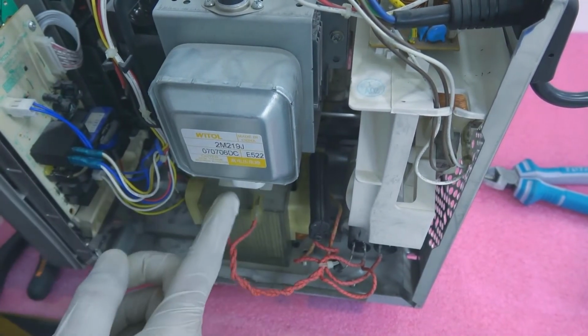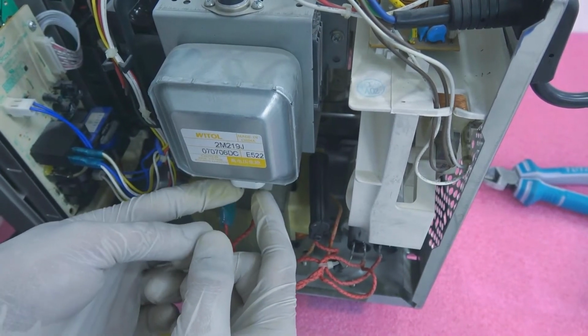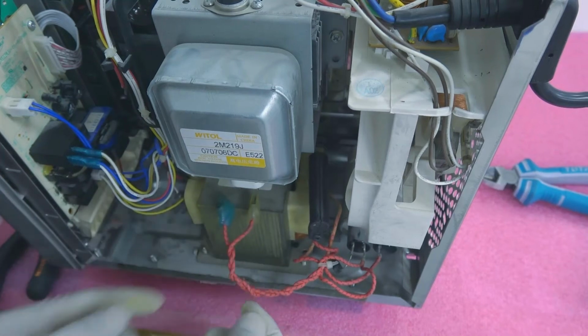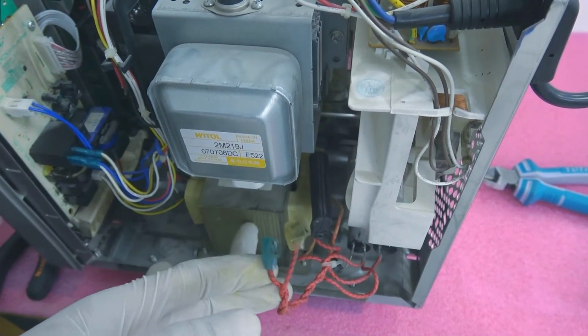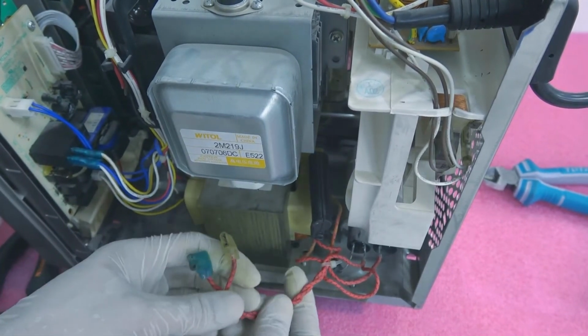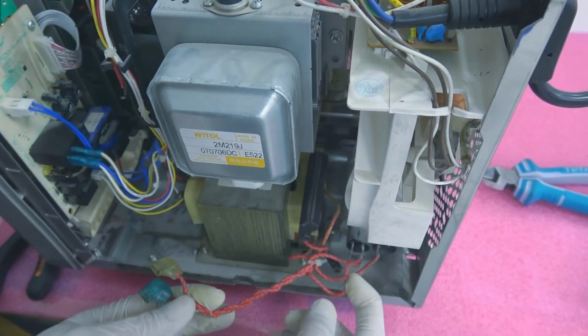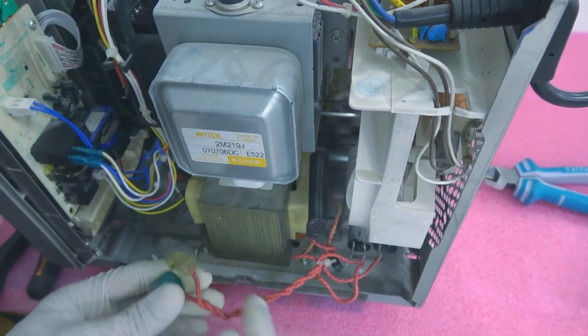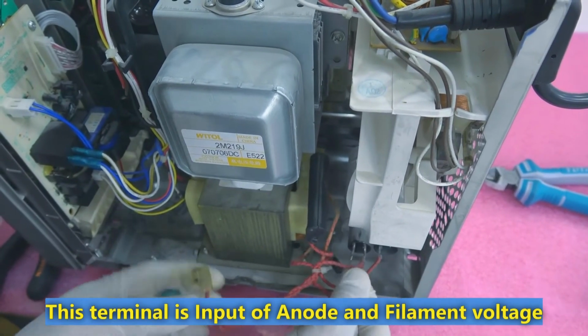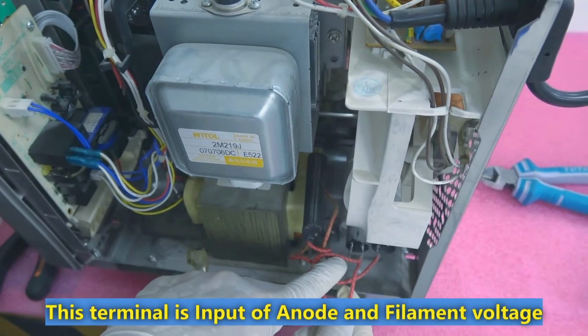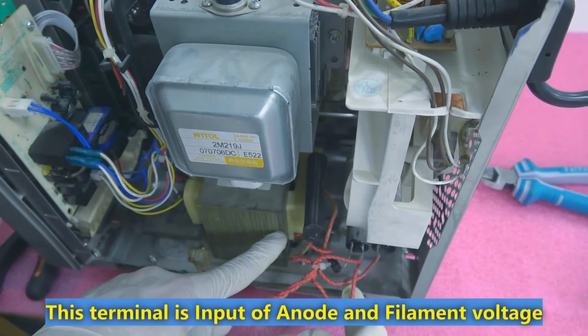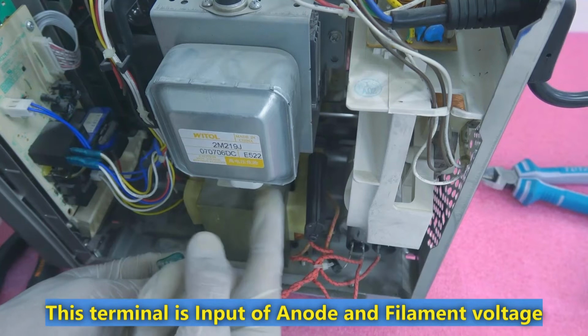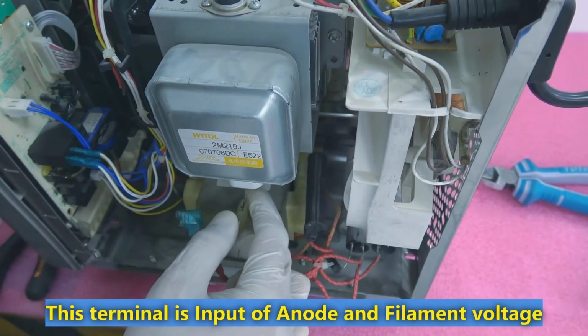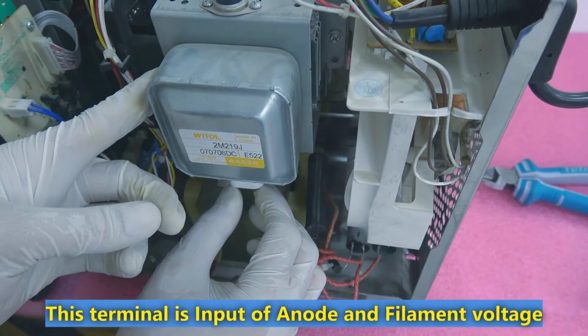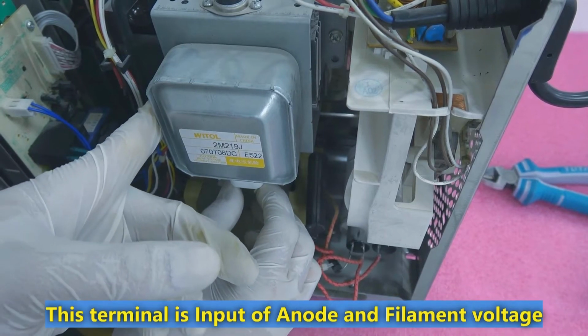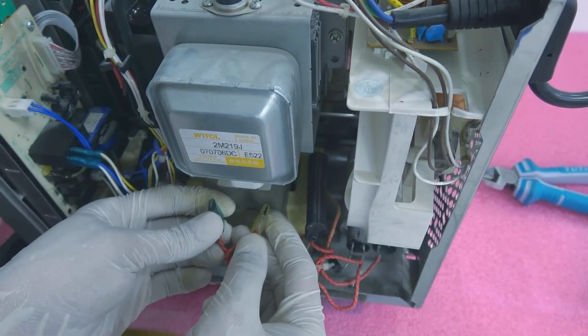This one, the terminal of this one is a filament, and the supply on this line is 3.5 volts AC. Because this wire is coming from the transformer, it's only turns, I think this one is 1 turn, and the other line is coming from the high voltage transformer combined on one line, like here, this one. Other line is from the high voltage transformer, and the other line is connected to the terminal of this magnetron. This terminal is connected directly to the bulb, the vacuum tube inside the magnetron, and it's giving supply.